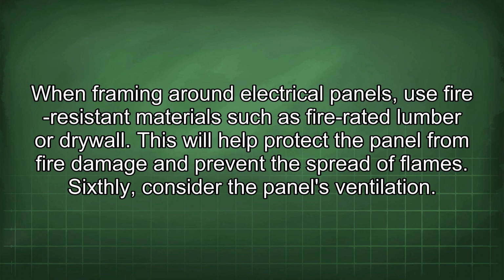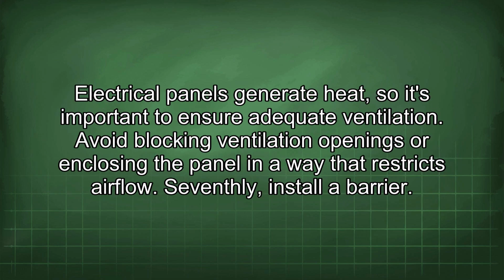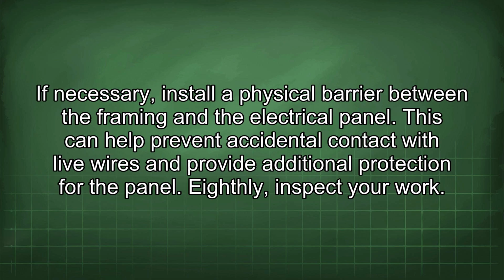Sixthly, consider the panel's ventilation. Electrical panels generate heat, so it's important to ensure adequate ventilation. Avoid blocking ventilation openings or enclosing the panel in a way that restricts airflow. Seventhly, install a barrier. If necessary, install a physical barrier between the framing and the electrical panel. This can help prevent accidental contact with live wires and provide additional protection for the panel.